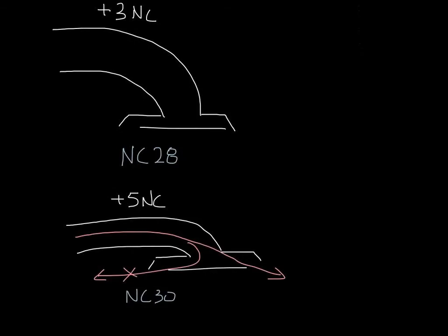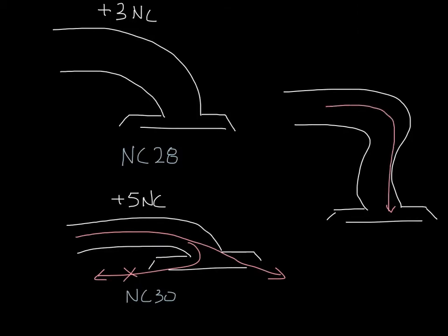The worst case is when the flex duct is kinked. This is pretty common, too. Even a small bend like this is going to force the air to one side of the ductwork and possibly out one side of the diffuser. This can add 7 to 9 NC to catalog data. So our diffuser that was cataloged at NC25 would sound more like NC32 or 34 installed like this.